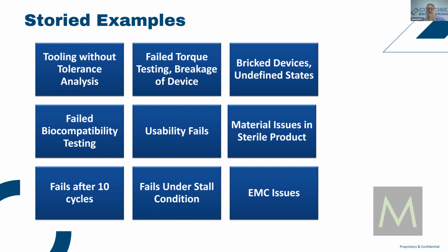And that generally results in a recall if you don't catch it early in the design. If you have a 3-year shelf life or something like that, it'll happen in the field, and then there's no way to resolve it other than bring all that product back. Thank you. Yeah, Justin, in addition to that, you've got various different ways to sterilize too. You've got ETO, you've got radiation, you've got E-beam, and all these do vastly different things, and they can interact with your product as well. So there's that kind of testing to determine what's the best way to sterilize. And then obviously the sterilization validation is something that has to be done to ensure that you meet all your parameters.